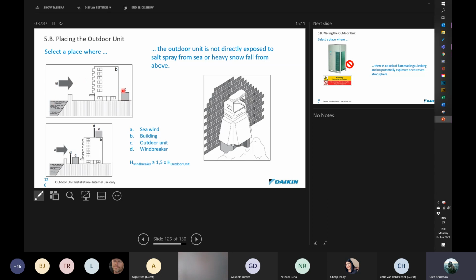Something to just remember is that we've seen such levels of salt buildup on units that there's actually been arcing taking place between the electrical terminals of the unit and also damage to PC boards. So be aware of that. If units are to be installed in this type of environment, the units also need to be treated. We would recommend a higher level of treatment when you're in a coastal environment or an industrially aggressive environment. So if you've got things like acid rain or certain chemicals in the environment. We've seen a catalytic factory in Port Elizabeth where the corrosion was quite severe around the factory area. So be aware of the type of environments that you're installing into. It might not necessarily be the sea that's a problem. It could just be some of the fallout from the actual processes taking place in the factory itself.